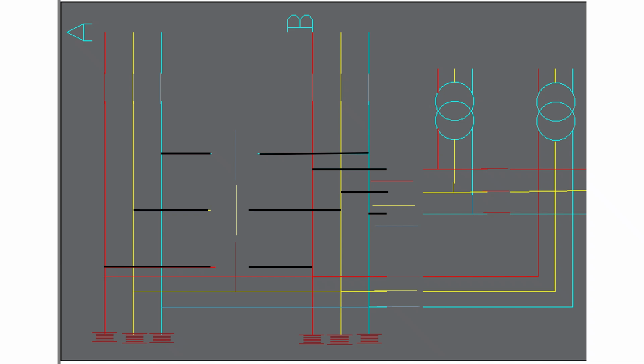So we have seen that power supply is possible both from A and B, and another bus coupler is kept between A and B, because if A supply fails, then we can extend the feed from B. If the isolator is defective, close to the first transformer of the B bay, so that feed can be extended via the A bay to the transformers. These are all alternate arrangements. Any problem, we can maintain the reliable power supply.